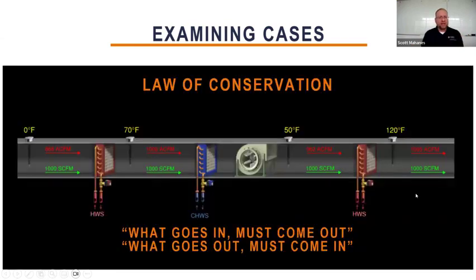So what's really happening in this case is at 0 degree air, I'm much higher in density. And so my volume goes down to 868. And when I preheat that to 70 degrees, I level off at 1,000 CFM, matching mass flow. And then if I subcool it down to 50, I increase density, I decrease volume to 962. And then when I reheat to 120, the density goes down again, the volume goes up. And it's just like a seesaw relationship.